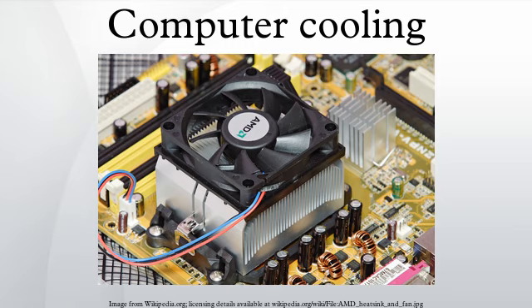This ideology has led to the investigation of integrating cooling elements into the computer chip. Currently there are two techniques, microchannel heat sinks and jet impingement cooling. In microchannel heat sinks, channels are fabricated into the silicon chip, and coolant is pumped through them. The channels are designed with very large surface area which results in large heat transfers. Heat dissipation of 3000 watts per cubic centimeter has been reported with this technique. The heat dissipation can be further increased if two-phase flow cooling is applied. Unfortunately, the system requires large pressure drops, due to the small channels, and the heat flux is lower with dielectric coolants used in electronic cooling.